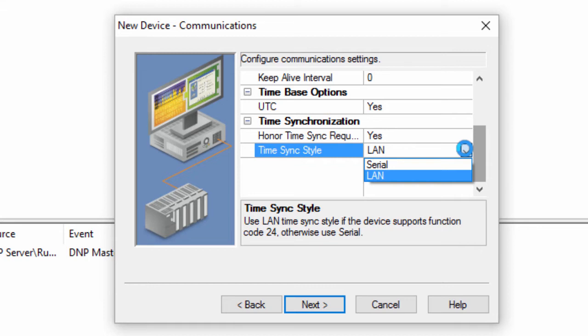When you use Serial, the master will make a delay measurement, meaning it calculates lag time, then sets the time in Object 50 Variation 1 to the lag corrected time. The remaining settings can usually be left at default.